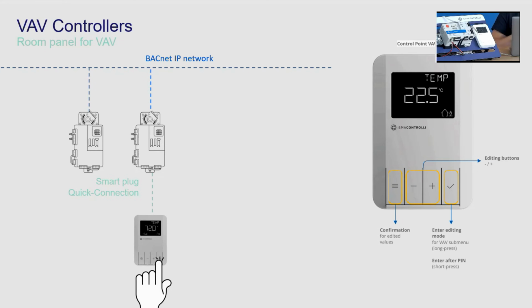So starting from the right, we have the OK confirmation button, which also gives us an option to access the hidden menu of the panel. So there's a password protected hidden menu that by accessing it directly, we can go into the VAV configuration, and after accepting the PIN that you can freely change, we can access all the software application configuration options for the VAV unit.